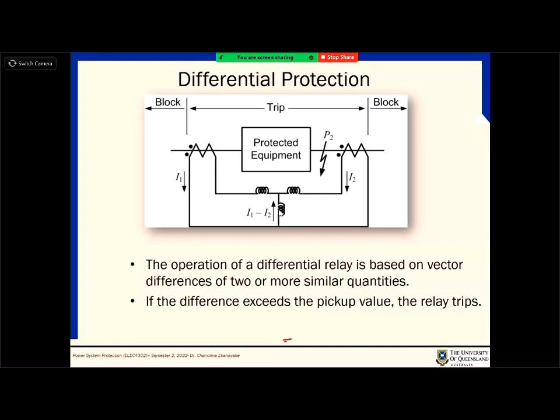Because there might always be some cases where noise current is going through it, or some small leakages in the equipment, or probably capacitive leakages, right? Because of them, this I1 minus I2 is not always 0. So you set it to a small value, let's say 0.1 amps. Above 0.1 amps, it will operate. That setting is called the pickup value. So if the differential current is above the pickup value, it will send the signal to the relay.